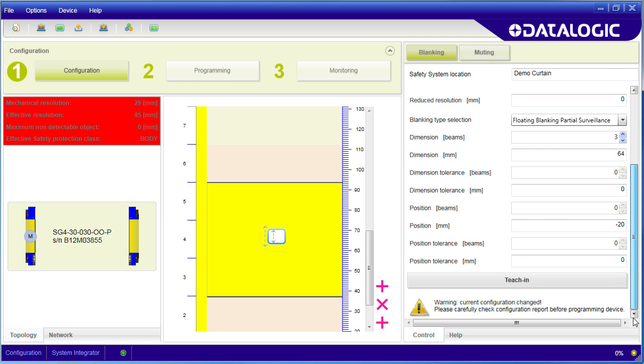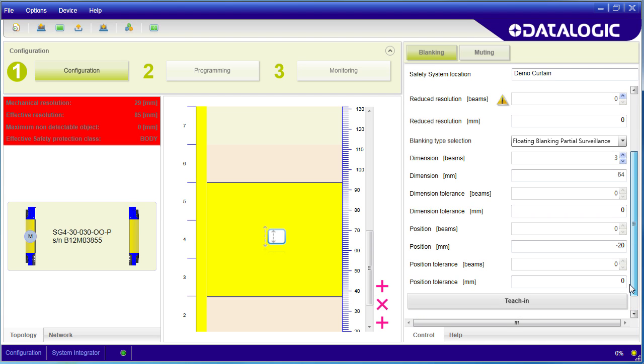The key thing to remember with fixed blanking is once you set it up, the sensor is always going to expect that blockage to be there. If the blockage goes away, the outputs will switch to safe mode.